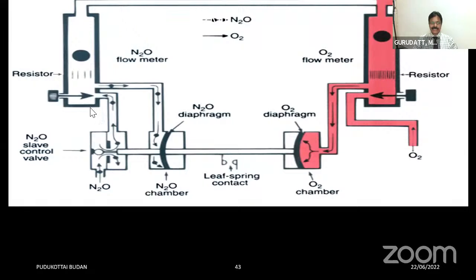In both the oxygen and nitrous oxide flow meters, we have the diaphragm. We have a resistor, and this resistor in the oxygen flow meter is a stronger resistor, and on the nitrous oxide side, it's a weaker resistor. These flow meters are also connected to two chambers. One is the oxygen chamber, another is the nitrous oxide chamber. Both these chambers also have diaphragms, and these diaphragms are connected by a shaft.